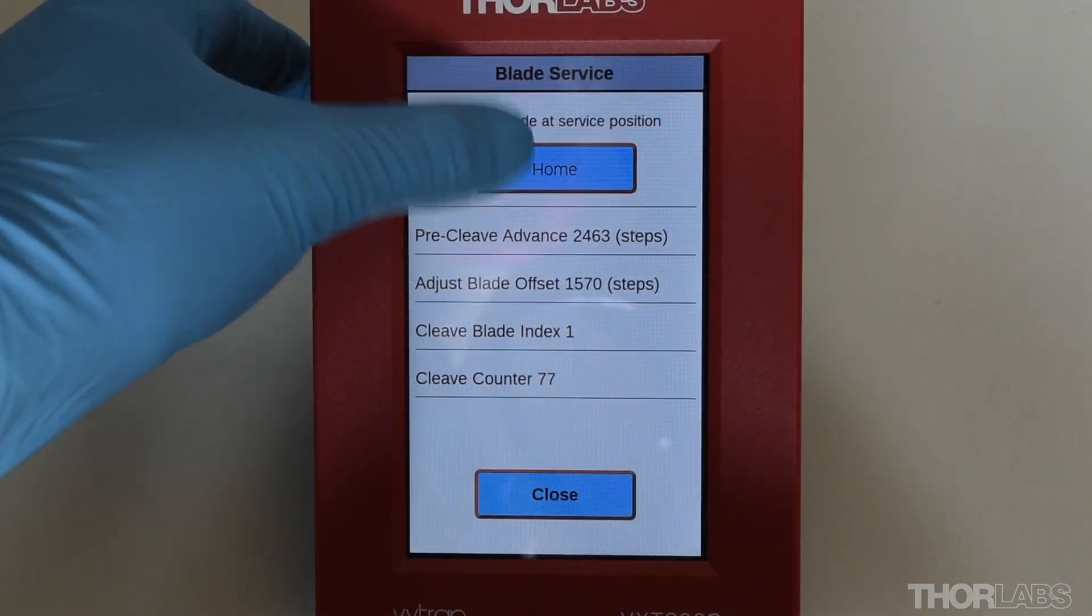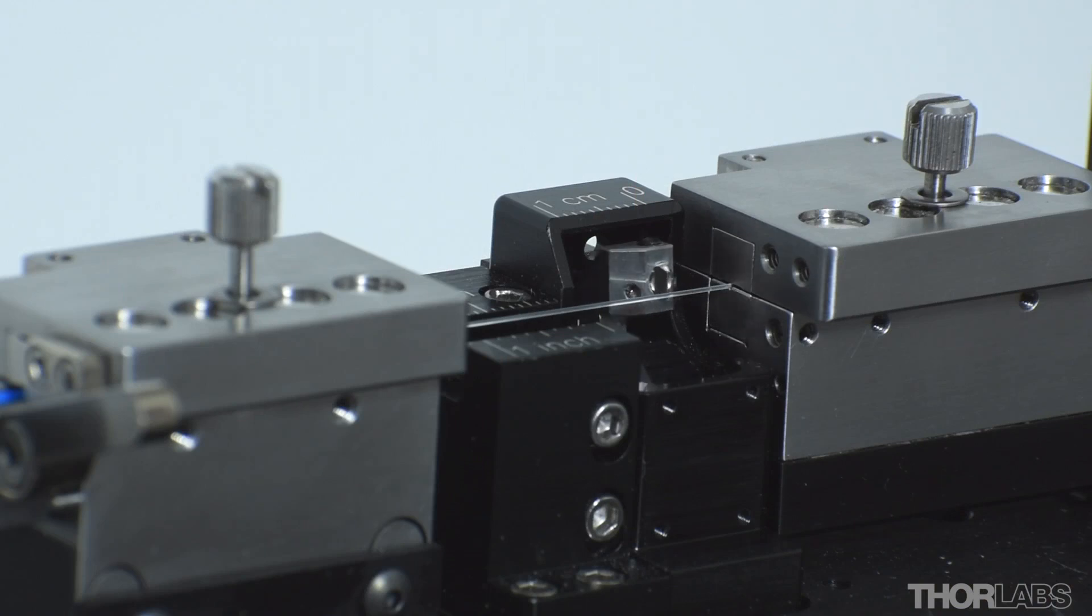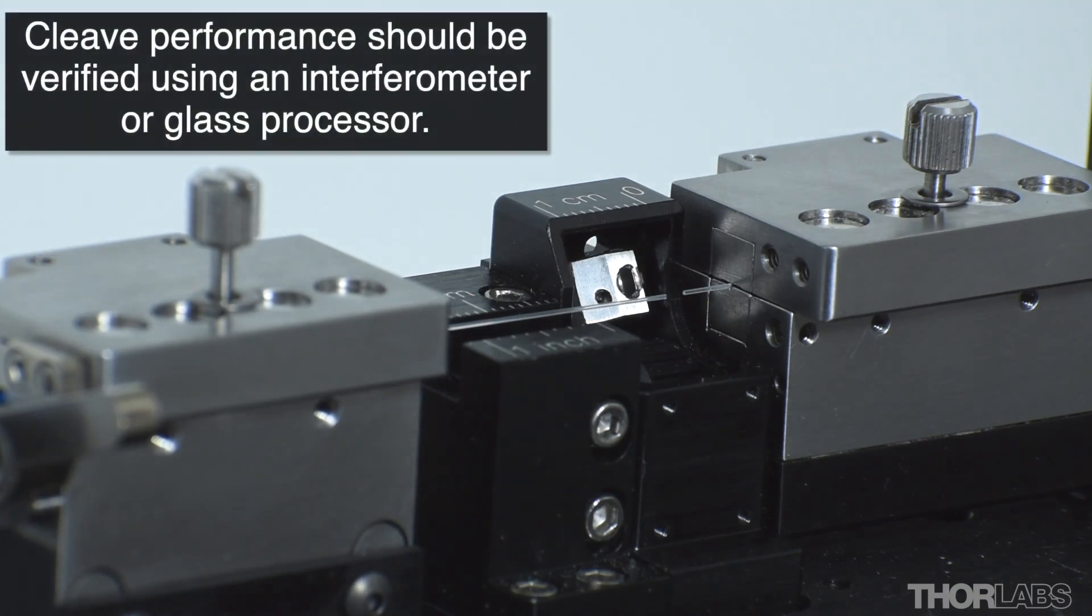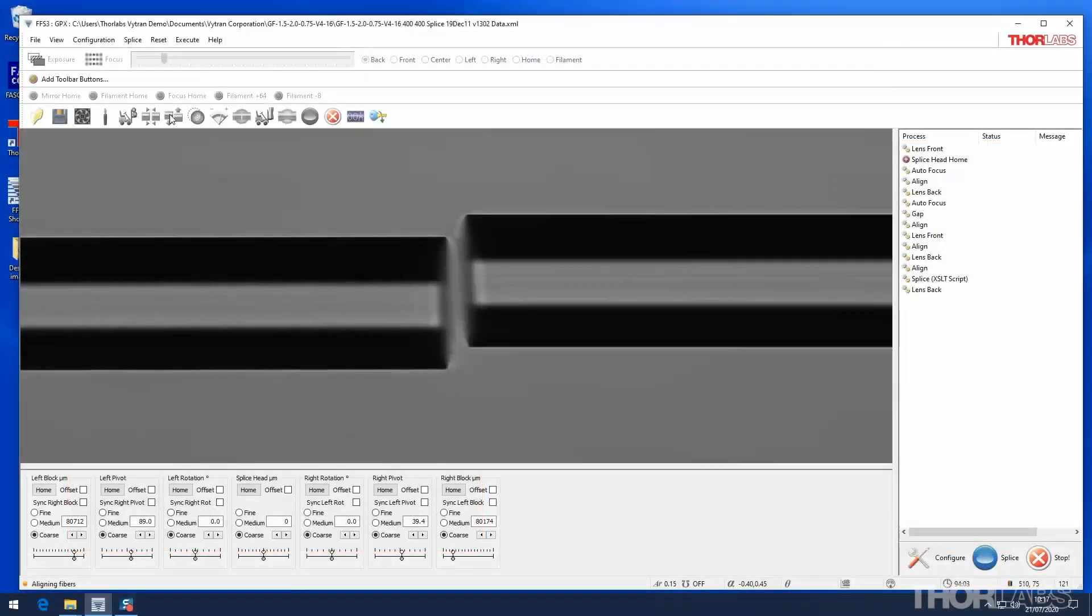After cleaning, use the handset to return the blade to its home position. Now load a new fiber into the unit and try cleaving once more. The cleaver performance can be verified by observing the cleaved fiber on an interferometer or using a glass processor.